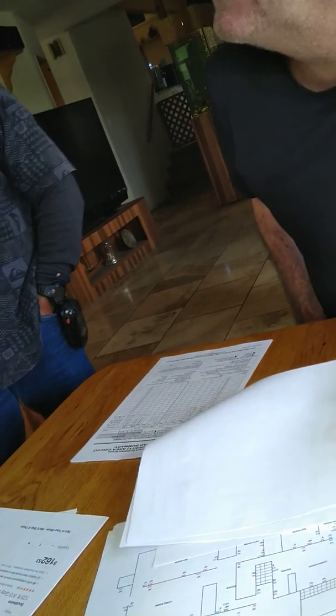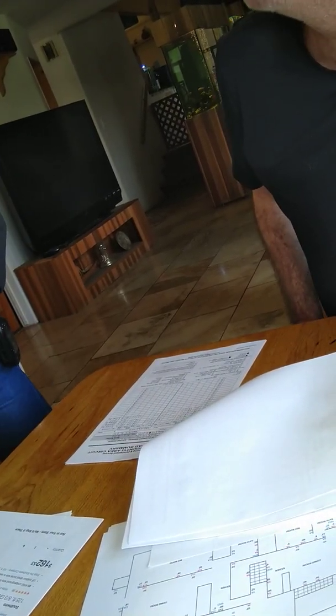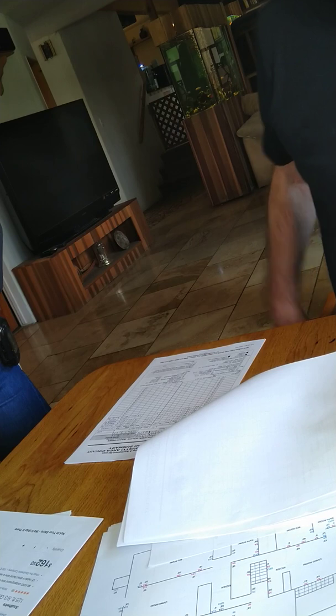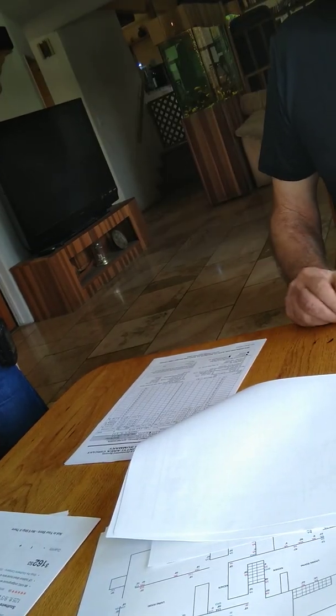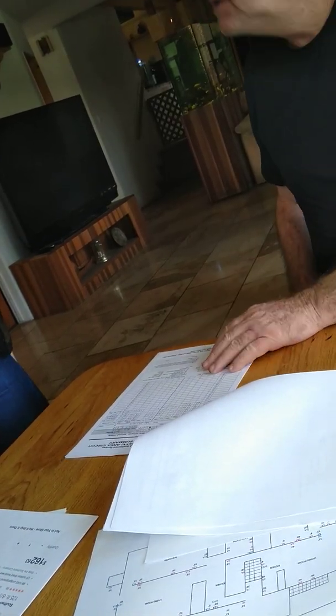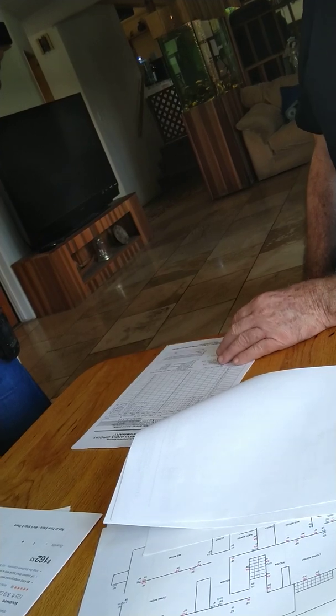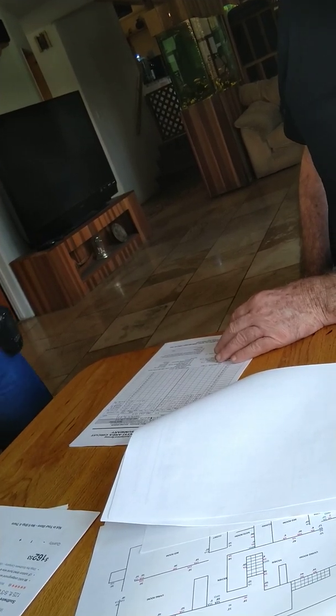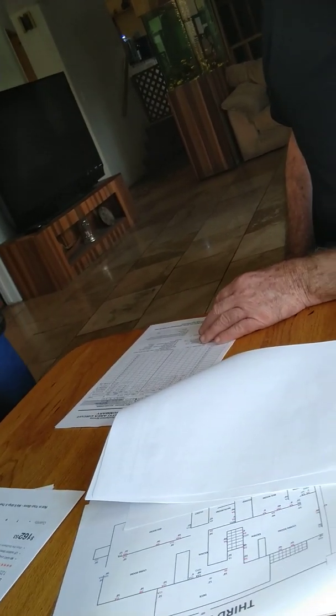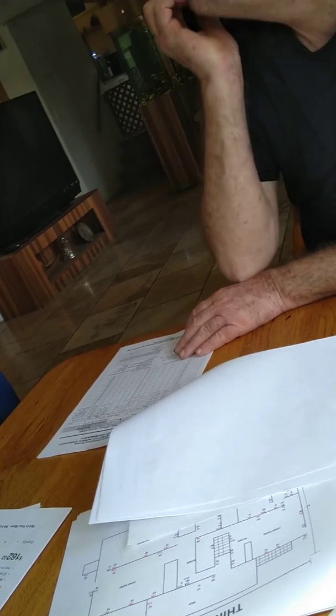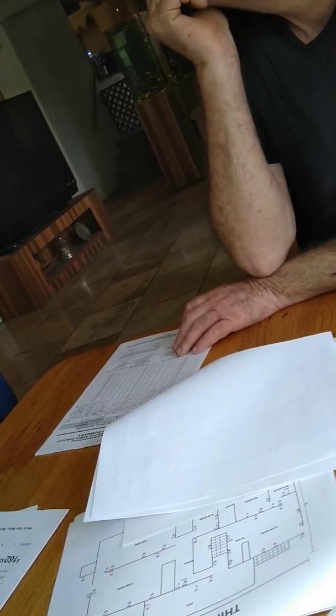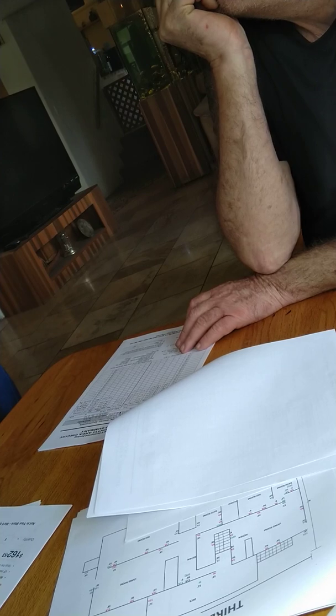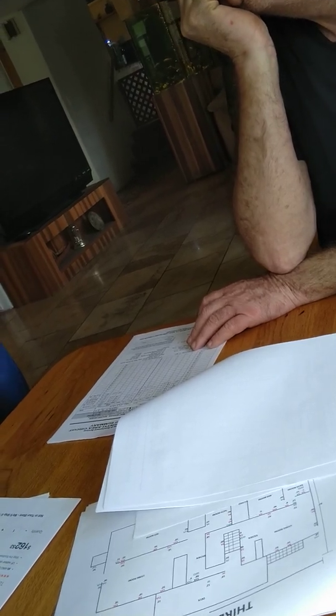Okay. Enrique, it's 8 gauge cable going to the panels. Sure. Well, before you continue, typically, let's see here. I think a number 8 is typically 40 amps. So on each sub panel, have you figured out what the load is on each sub panel?